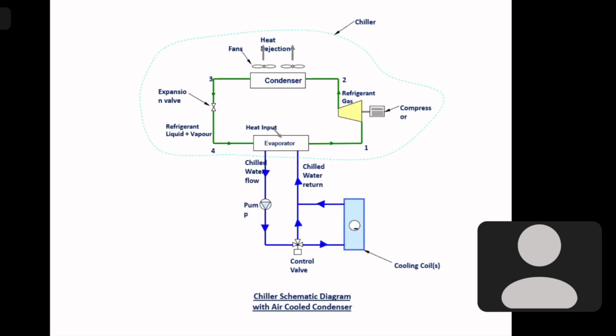So here, the advantage is that if the premises you need to cool have various rooms spread out, then taking refrigerant over a longer distance to various rooms is not very effective, because the refrigerant may get heated up, and the compressor may need to be a very high pressure compressor. To avoid that, we first cool some water by expansion of refrigerant gas, and we take that cooled water to various areas for use in the cooling coil. So this is called a chilled water system.